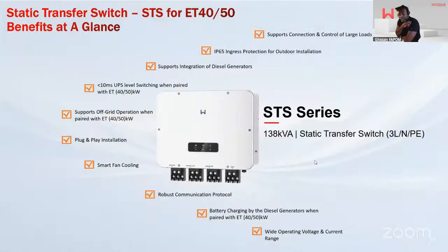Now enters the STS box. In order to overcome this limitation I talked about, we have the STS box, which has been designed for the bigger platform, ET40 and 50. The ET40 and 50 can be bought without the cabinet if you don't need any backup load or any generator compatibility. You do not need an STS box. The STS box is also designed for cases where, with a 50 kilowatt inverter, someone has a load bigger than 50 kilowatt. So this STS box would handle all the way to 138 kilowatt of load. The way you achieve it is you take some from the grid and some from the generator that you have connected to achieve a bigger load for your system.